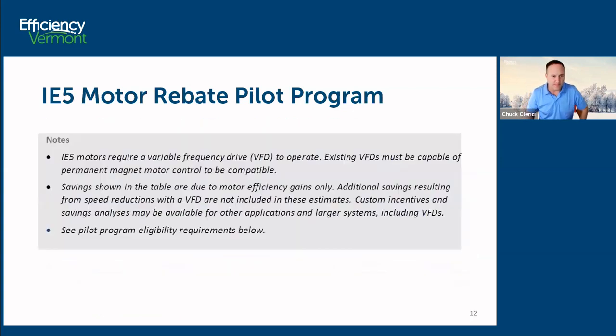Very important point: IE5 motors require a variable frequency drive to operate. So if you have an existing IE3 motor or IE2 motor, and it doesn't have a drive, you're entertaining a motor and drive upgrade, not just a straight motor swap. To make matters a little bit more careful, let's say, any existing VFDs must be capable of operating permanent magnet motors, which are the IE5 motors. So there's a little extra homework here, and we will help you with this.